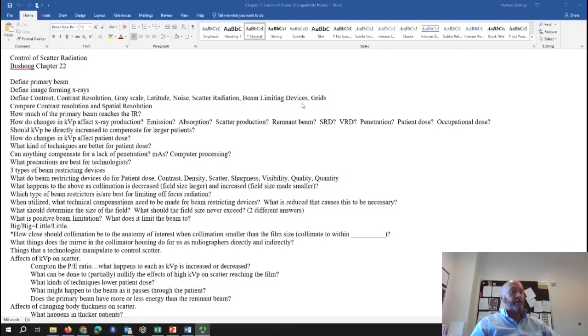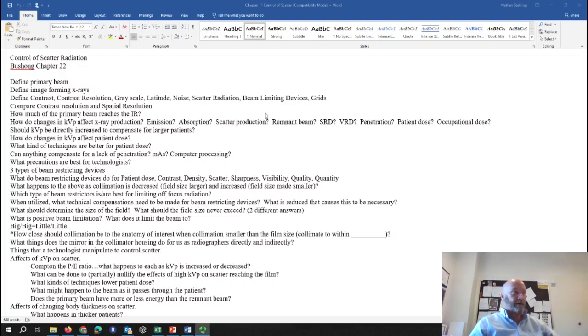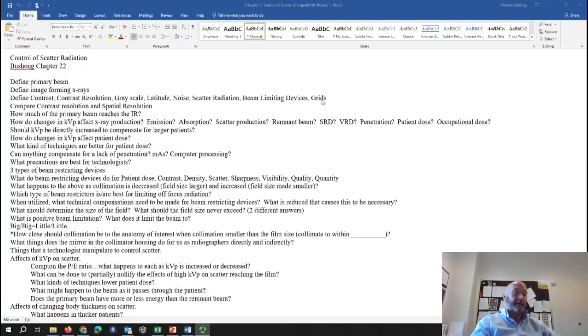A beam-limiting device is anything that restricts the size of the beam of radiation and how much tissue you expose to the x-ray beam. Collimators, cones, and diaphragms are all types of beam-limiting devices, as opposed to grids. Beam-limiting devices prevent scatter from being created, and grids clean up scatter radiation after it's created.